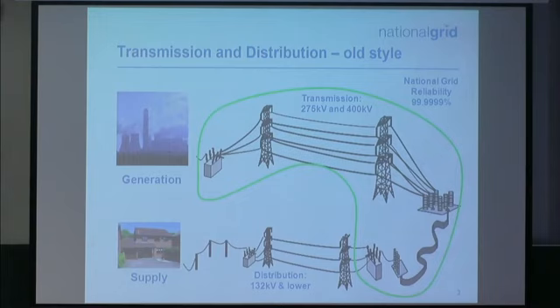When a bit of the distribution network fails, you might lose electricity to a street, or to a town. That would be bad. But if we lose reliability at one of our main transformers, we could disconnect Birmingham, Leeds and Liverpool or similar. So our failures, although very rare, when they do occur have much more impact on a far larger number of people than a distribution failure, which is why we're so keen to keep this figure as high as possible.